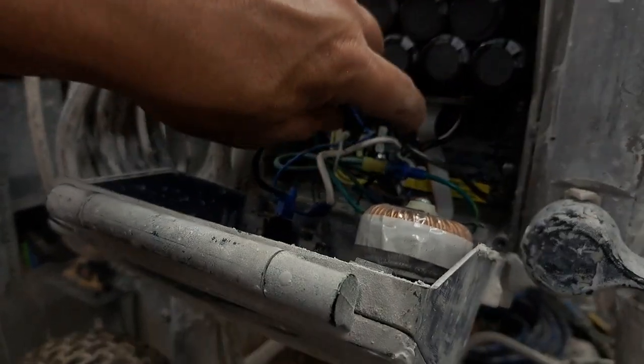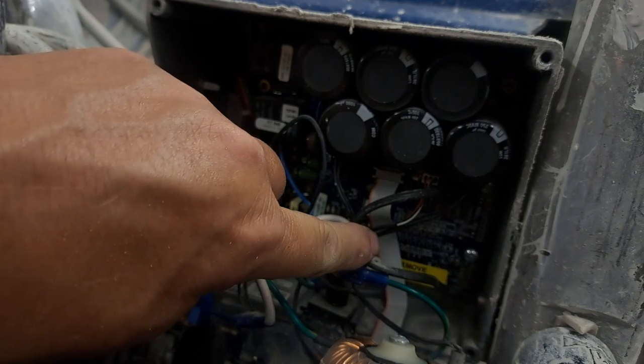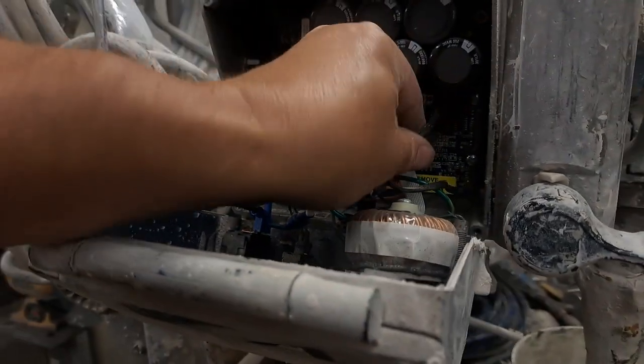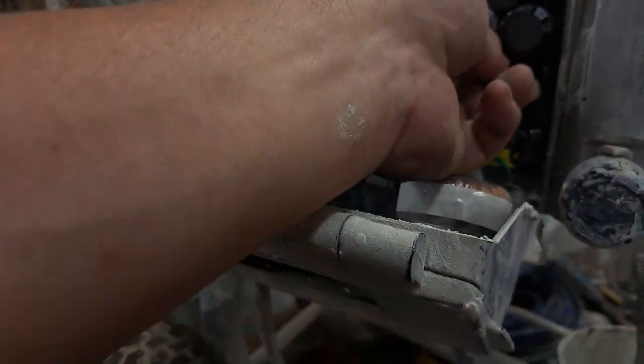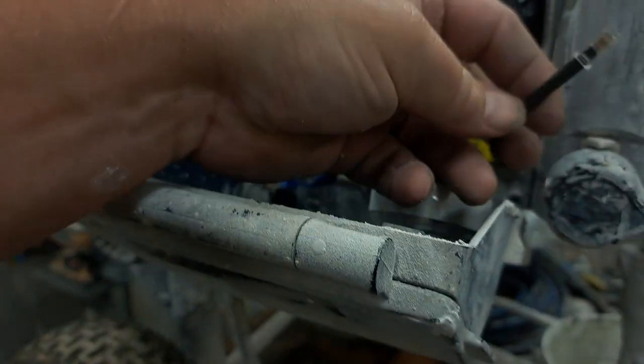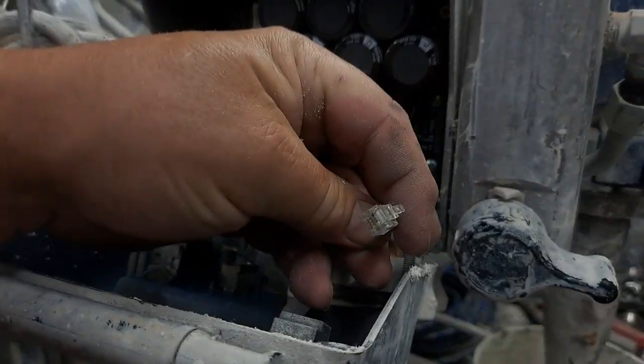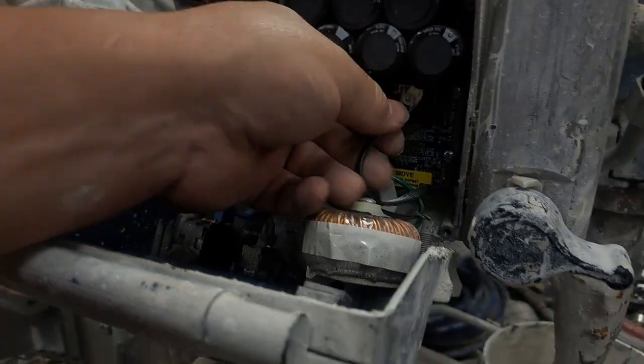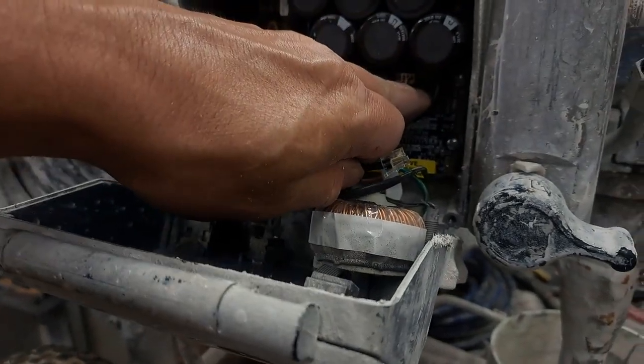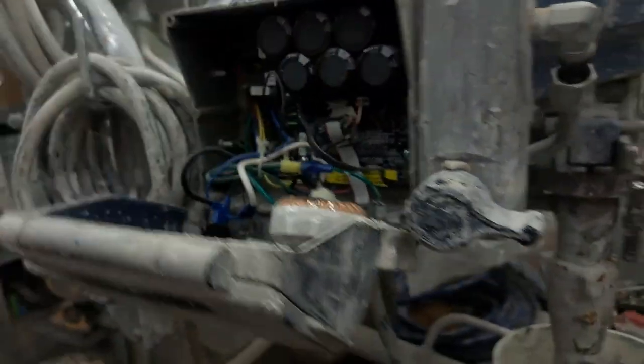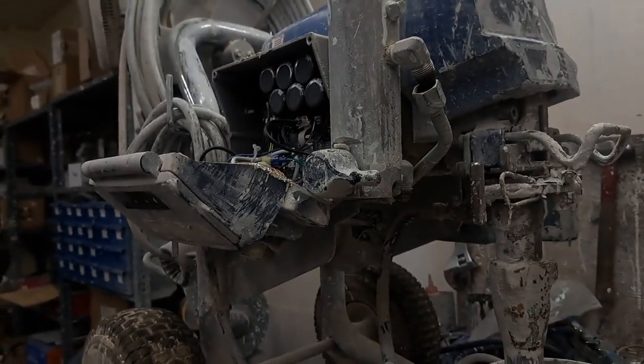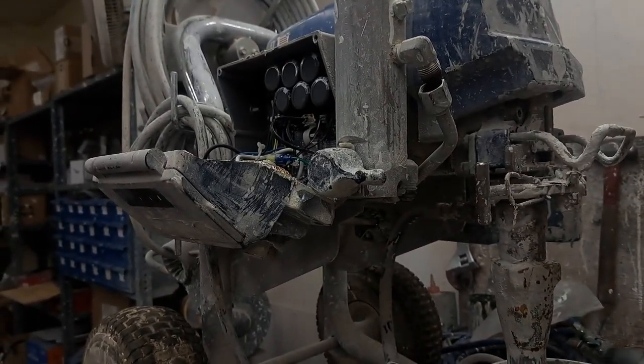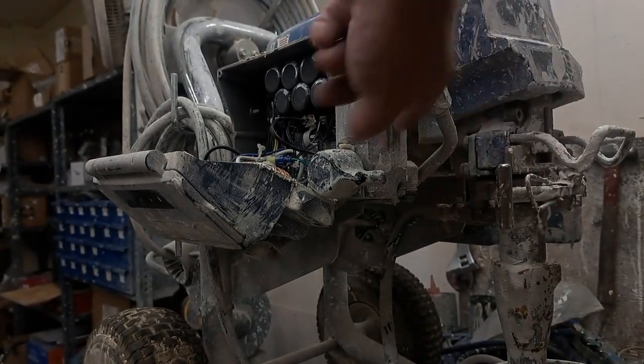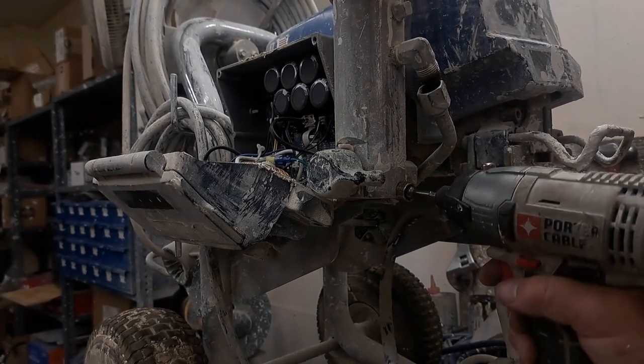So there's the plug for the transducer, and it plugs in like an old phone jack, for those who've been around long enough to know what that is. You just push the clip and pull it out. Like I said, if it falls, it'll damage that port right there, and if it damages the port, you got to replace the board. We don't want to do that because that's about, like I say, $800, $850. So now we're going to remove the filter housing.